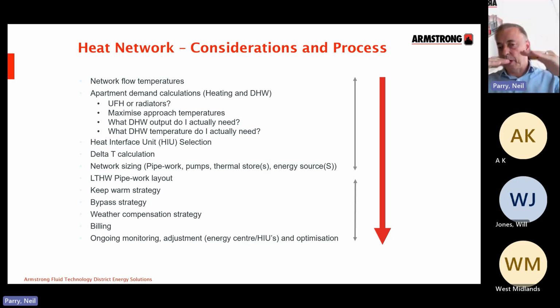Because if you start to weather compensate and you end up with a flow temperature that is at or below the set point of the HIUs in the apartments, as soon as it drops below, the HIU control valves will open up to try and achieve a flow temperature that is impossible. And what will happen then is you get maximum flow all over the building and the system will actually crash.